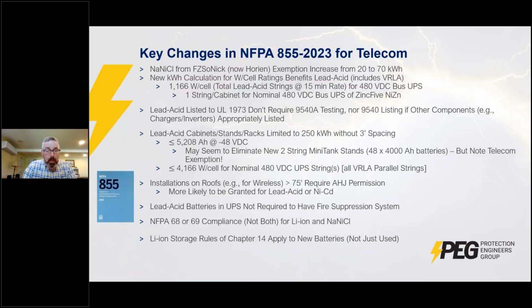In addition, one of the concerns is rooftop installations. Firefighters and responders have a big concern with rooftop access for both battery systems and also solar systems. As Curtis mentioned before, there's a lot of interest in these solar applications tied with the batteries. Solar systems are often on the roofs, and there's often batteries with them, and there's often telecom applications of cellular equipment on roofs with batteries. So that's a concern for the firefighters. They don't want to be too close to the roof. They don't want to be falling off a slippery roof. Most of the telecom sites are on a flat roof, as opposed to maybe the solar sites. But rooftop access is something that they're concerned about. They want to make sure that's managed and safe.